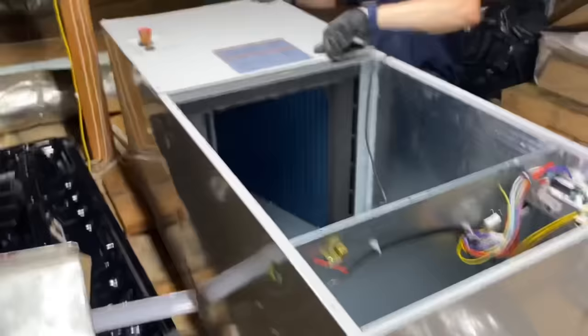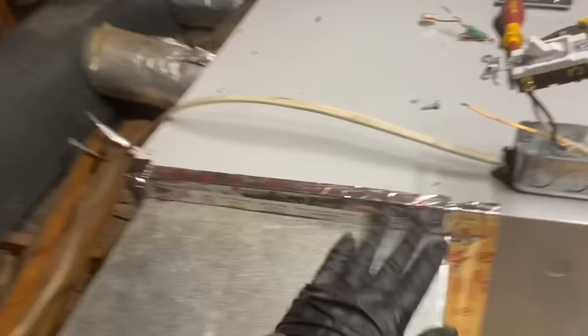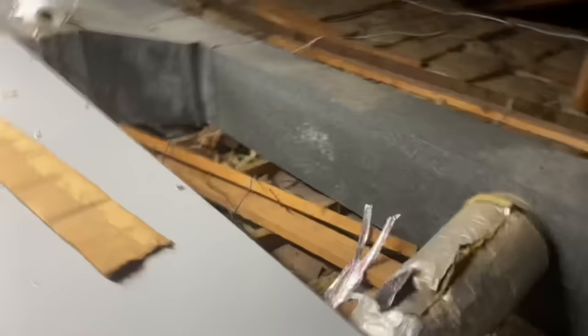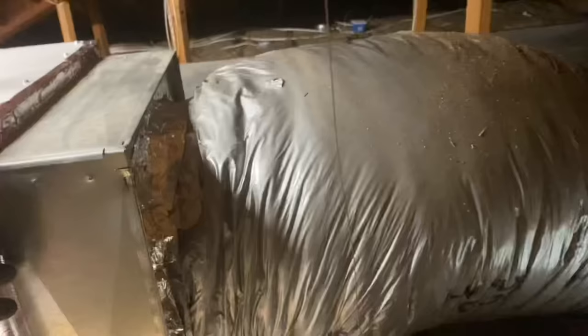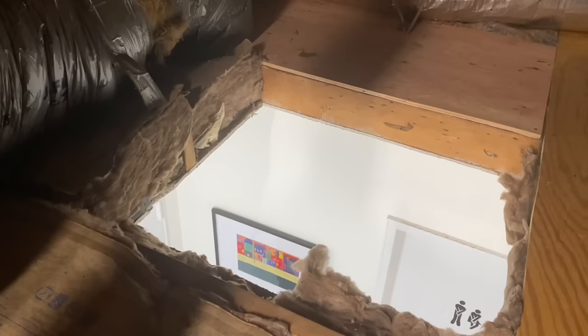Alright. That looks really, really nice. Get you down below and see everything in there. Everything worked out perfectly with the supply plenum. I got the mastic tape wrapped around all of my flanges. I'll show you the wiring in a minute. In my return, very, very nice. All my sides, my bottom, and far side, all looks perfect. Very, very nice. He's learning. And when we have some more 16-inch flex, we'll replace that as well. Okay, we'll put back our plenum box. Filter wheel box. We'll put that back shortly.